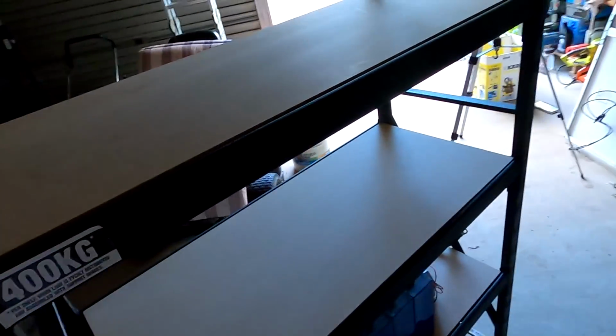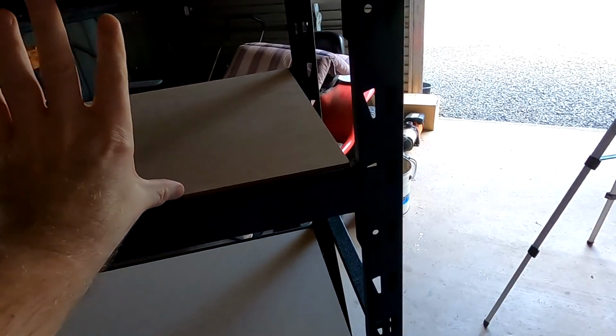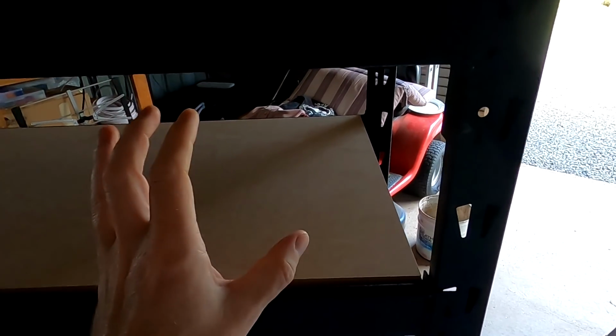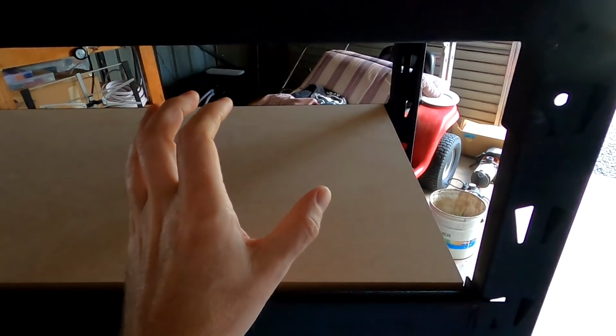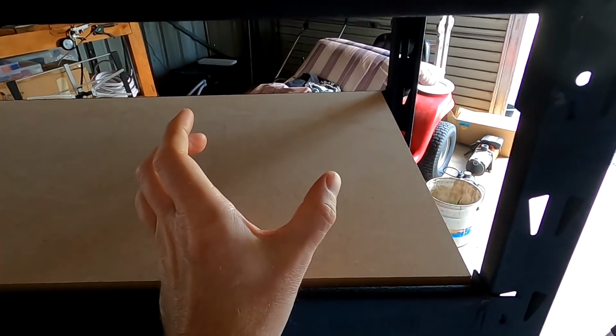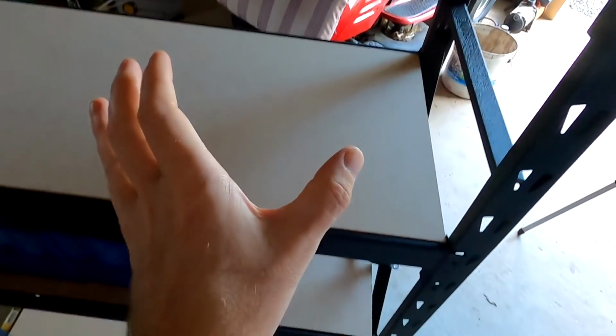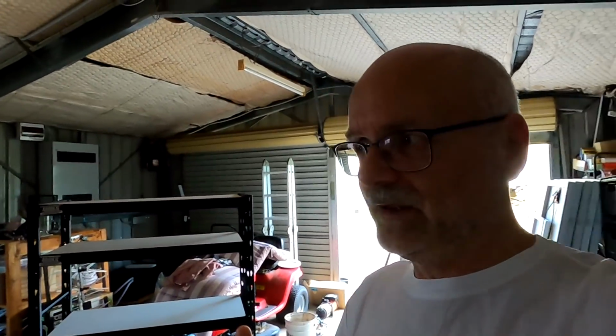And then here in the top compartment, what are we going to do here? I would like to have a main switch, a 250 amp circuit breaker switch and isolator for the whole battery cabinet. There are some available from Noark as well. Not quite cheap, but they also come with an auxiliary switch.